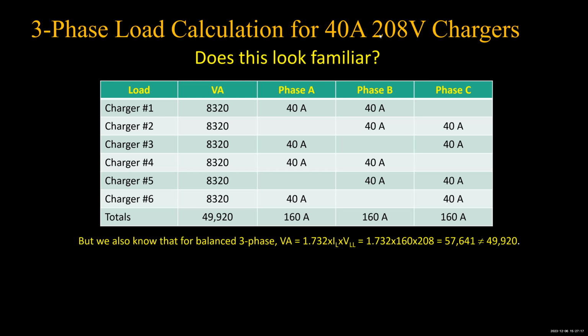That would say the neutral current is significant then, because normally the neutral current is simply the difference between all the other currents in the lines. I need to look into this, Brad. This is excellent. First I've heard of that. First data. I need to find out exactly what goes on here. So in terms of, and of course, the local jurisdiction is always the final word on this. And this is assuming that the neutral currents are not going to be a problem, but certainly, that's going to give you, and of course, you have to have all 4 conductors in the same conduit, unless you're running parallel conductors. So that would be a derate.